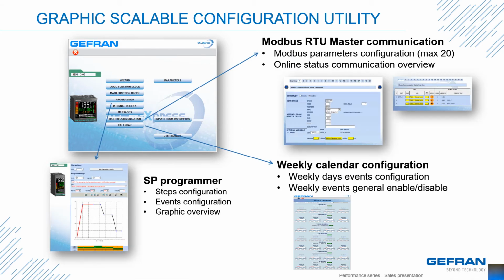The configuration tool lets you program the MODBUS RTU master communications. If you choose to talk to other Gefran products or third-party products, then you would set them up here. In my previous examples, I showed the Gefran GTF power controller. I mostly assumed a 4 to 20 milliamp output to the GTF. However, I could replace this by using the MODBUS master communications and control the GTF via communications.